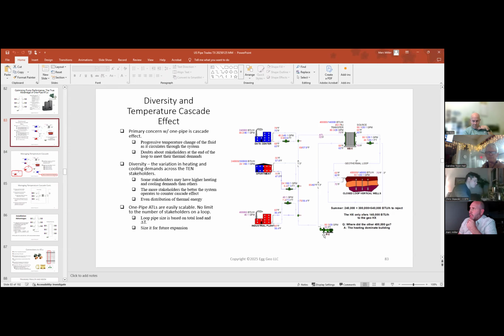And this loop is pump controlled. It's not control valve controlled, which we're all used to, or I should say those of us in the trade, remember the audience. So this is in summer mode. We have a heating dominant stakeholder, this person here producing 300,000 BTUs, and we have this other person here producing 240,000 BTUs, which is about 10 tons. So that means that in a traditional system, we would in theory have to reject 540,000 BTUs to the earth, because 240 and 300,000.